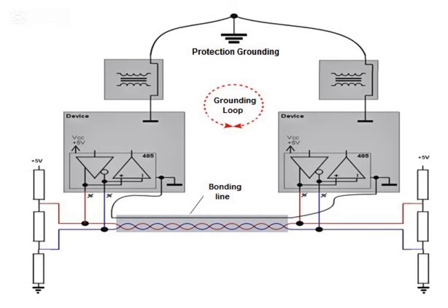Types: single point grounding, best for low frequency signals to avoid ground loops. Multi-point grounding, used in high frequency systems to minimize impedance. 3. Shielding. Purpose: protects signals from electromagnetic interference, EMI, and radio frequency interference, RFI. Applications: cable shielding prevents noise coupling in instrument cables, for example, thermocouples, RTDs, analog signals. Equipment shielding: metal enclosures block external EMI.